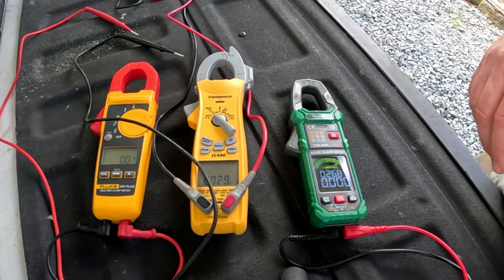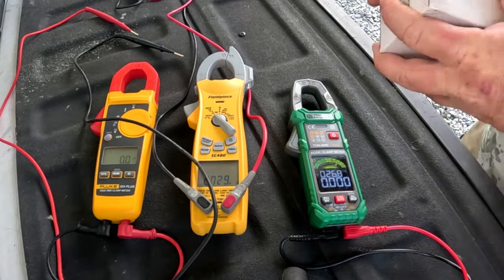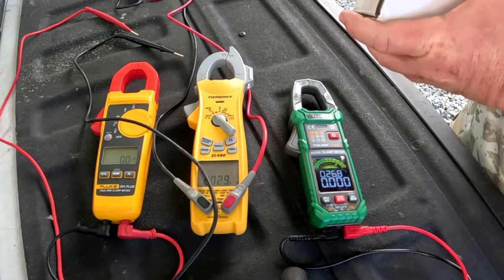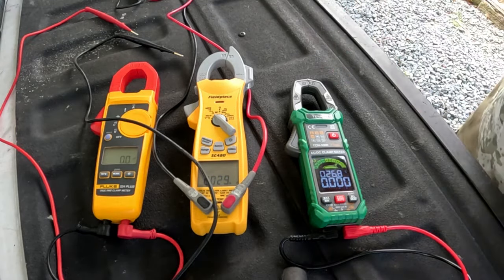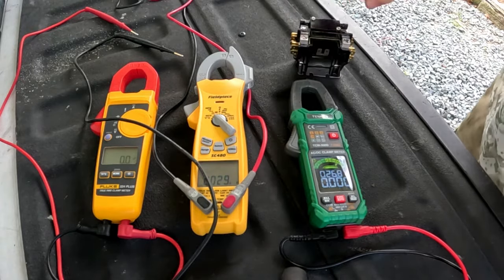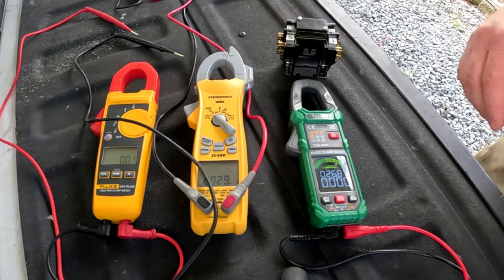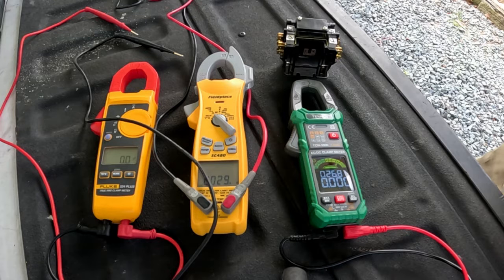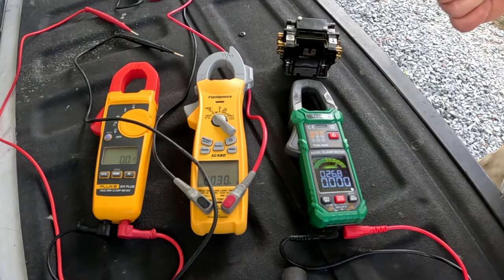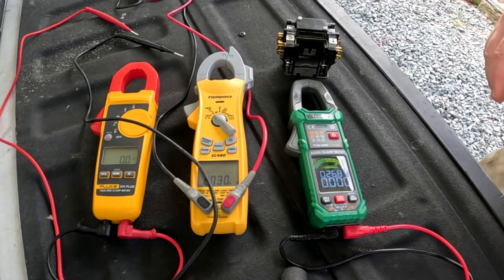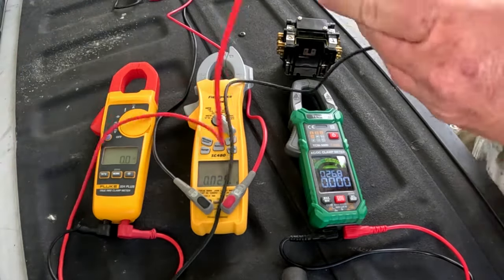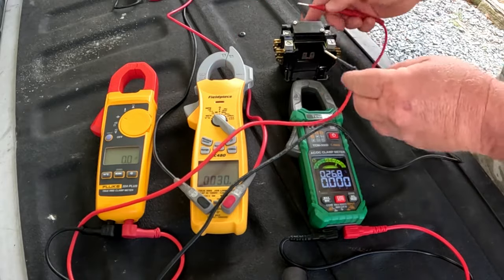So now let's ohm out a contactor real quick. I'm just trying to do some basic things that come up on the job most of the time. So we're going to check a contactor - we got a blowing fuse in the air handler. Every time the thermostat calls, as soon as it calls for Y, your fuse blows. So we're going to ohm the contactor out and see if that's the source of our short.